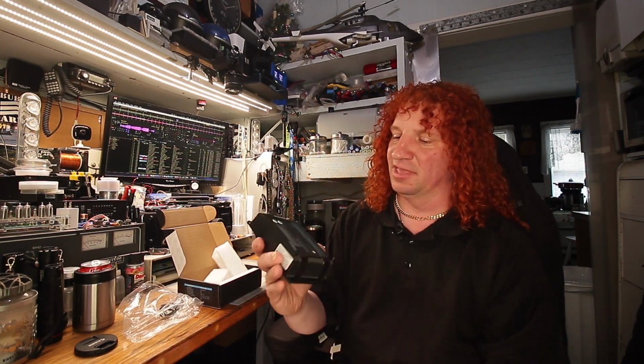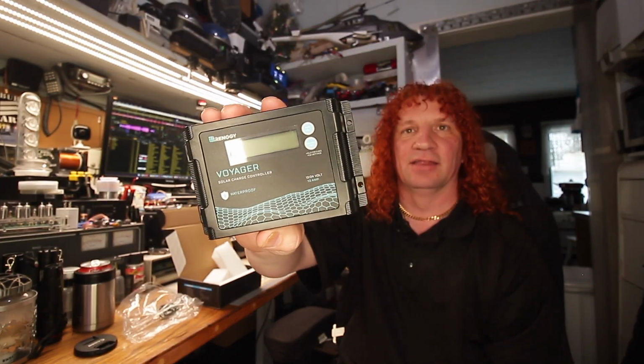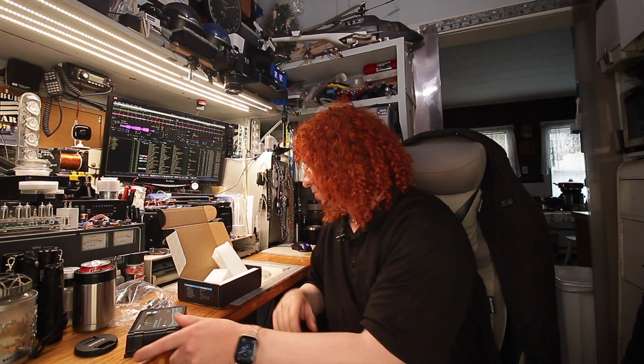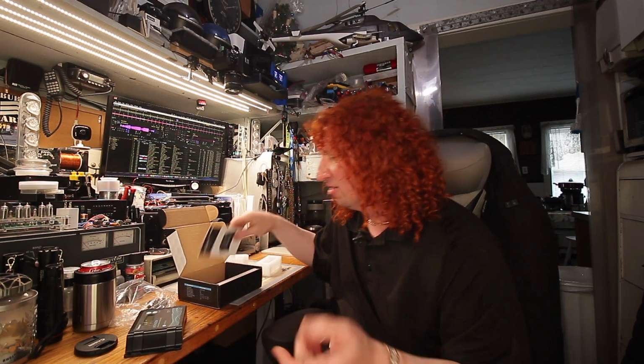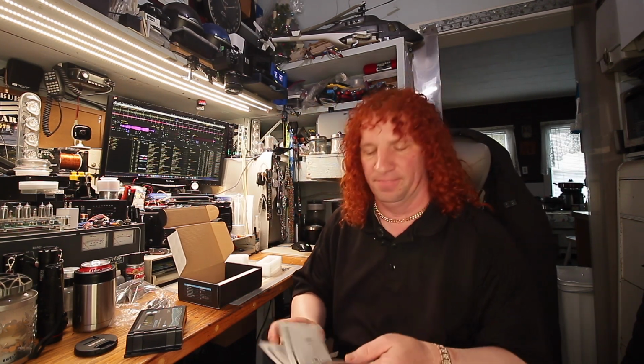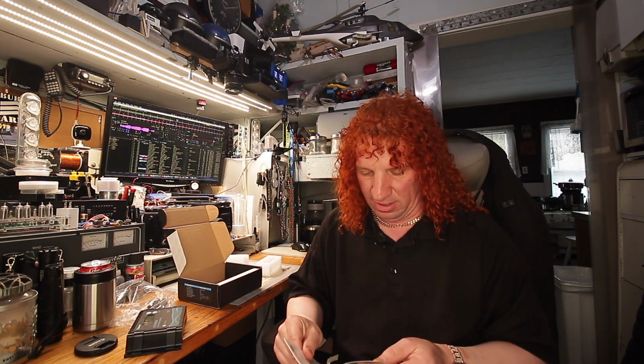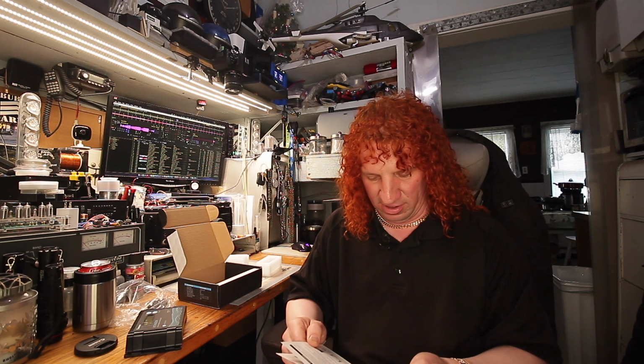It's just a big black box, and I have to set it up for charging a lithium battery. This is a 12 or 24 volt, 10 amp pulse width modulated charging system that's good for your gel cells, absorbed glass mat, flooded lead acid, and lithium. I've already set this up to be a lithium battery charger, and it has all the good stuff to bring it up to charge, maintain, and float charge. It's good up to 10 amps.